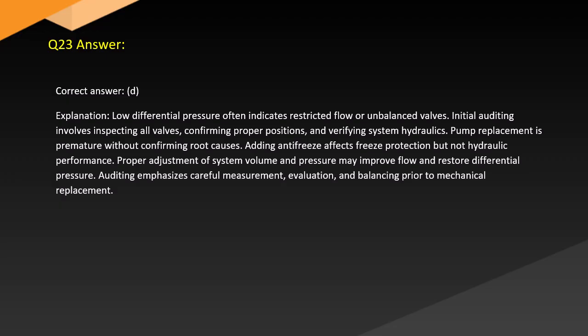Answer. Correct answer. D. Explanation. Low differential pressure often indicates restricted flow or unbalanced valves. Initial auditing involves inspecting all valves, confirming proper positions, and verifying system hydraulics. Pump replacement is premature without confirming root causes. Adding antifreeze affects freeze protection but not hydraulic performance. Proper adjustment of system volume and pressure may improve flow and restore differential pressure. Auditing emphasizes careful measurement, evaluation, and balancing prior to mechanical replacement.